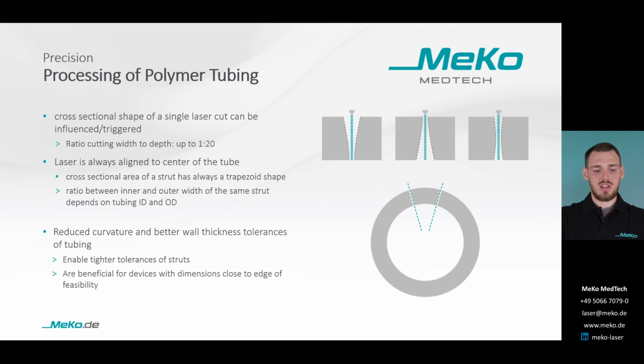If we have a look at processing a polymer tubing, the laser is always aligned to the center of the tube, as sketched in the bottom right figure. So the resulting cross-sectional area of the laser-cut strut always has a trapezoid shape, and the ratio between inner and outer strut width depends on the tubing geometry. For the best possible result, these parameters must be very well adjusted, which in turn requires high dimensional uniformity and straightness of the tubing.